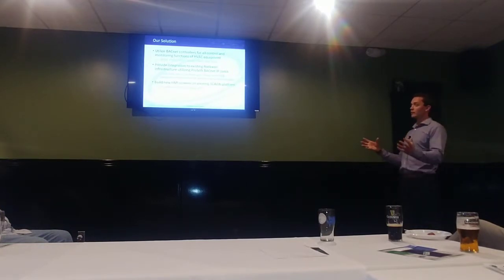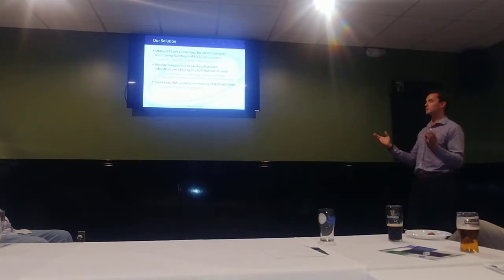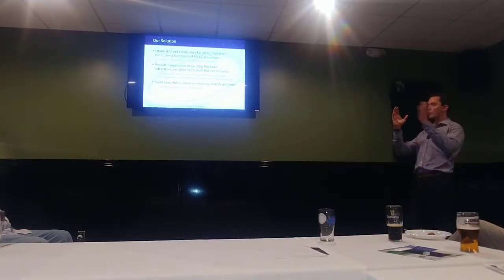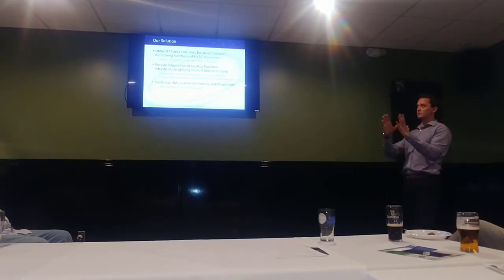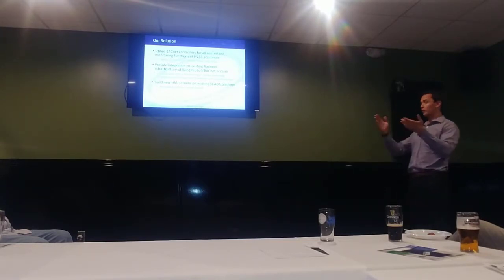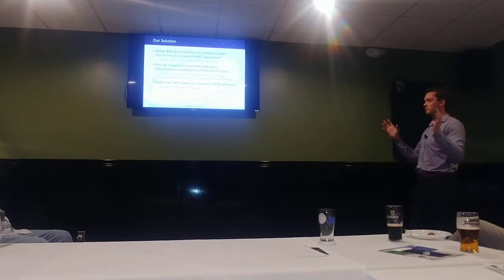We also needed to provide integration of all these BAS controllers into their SCADA platform. There's a plethora of ways you can do it, but the way we decided to do it here was to use what's called ProSoft BACnet IP cards. These are basically cards that go into a ControlLogix chassis and connect BACnet IP to your BACnet network, and there's basically a CSV file in these cards, and you map the points over. We had a handful of ControlLogix in each building. We put our ProSoft cards in, did our configuration, mapped all our BACnet points, and brought them right into Rockwell through the ControlLogix.